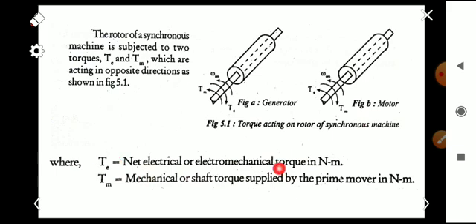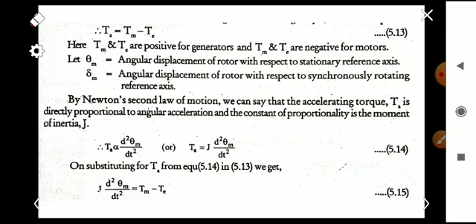The rotor of a synchronous machine is subjected to two different torques: T_E and T_M. T_E is the net electrical or electromagnetic torque in Newton-meters, and T_M is the mechanical or shaft torque supplied by the prime mover. Under steady-state operating conditions, T_E and T_M are equal and the machine runs at synchronous speed. If there is a difference between these two torques, the rotor will have an accelerating or decelerating torque, denoted T_A — the net accelerating torque.